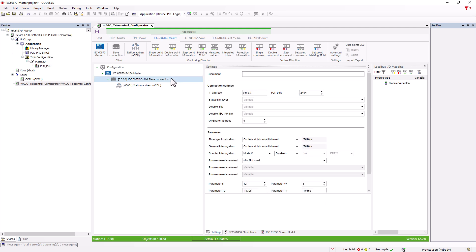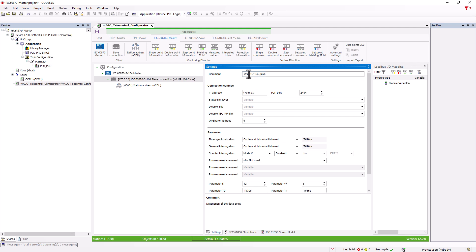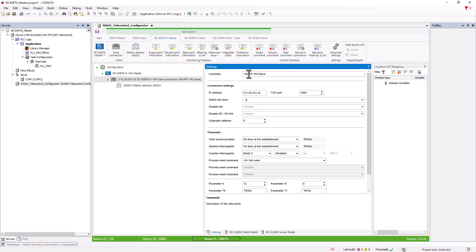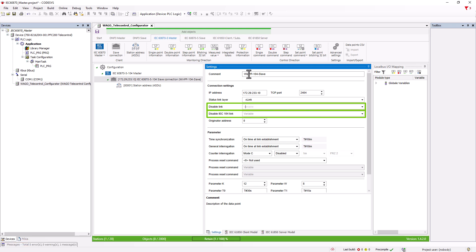We can enter a comment in the slave communication settings, then we enter the IP address and TCP port of the slave. For the link layer status, we set a bool variable that becomes true when communication is active. For disable link and disable IEC 104 link, we can specify variables that deactivate the communication with the slave.